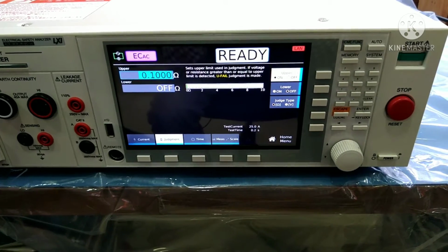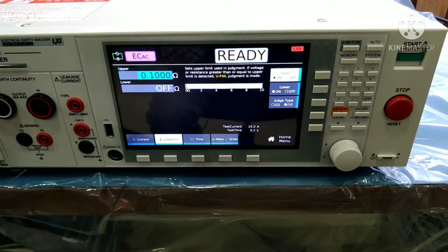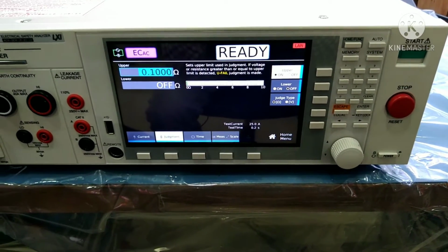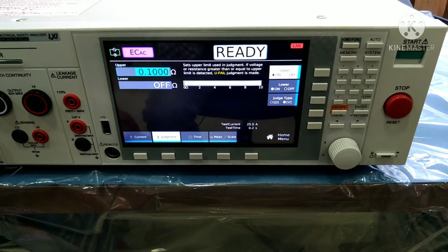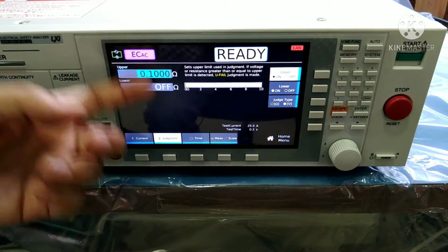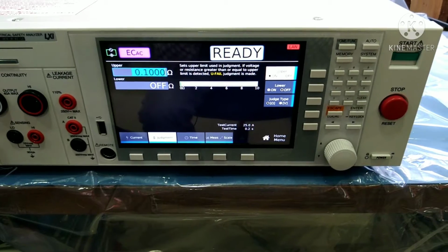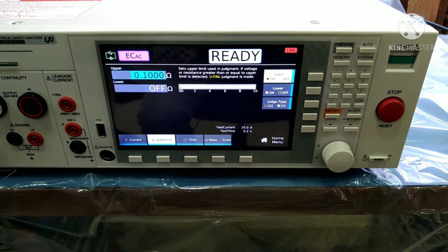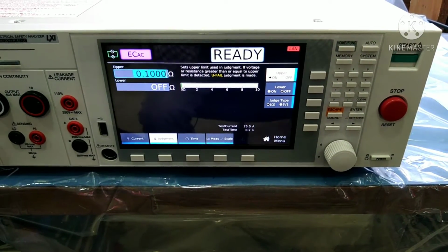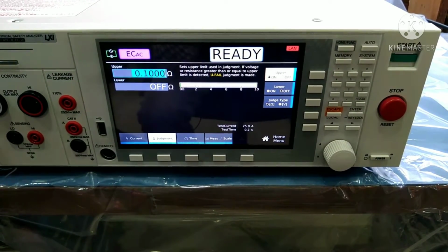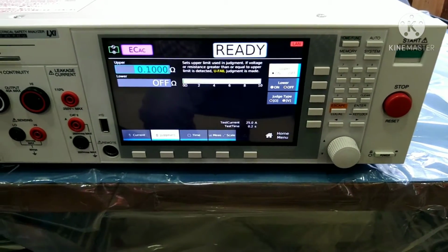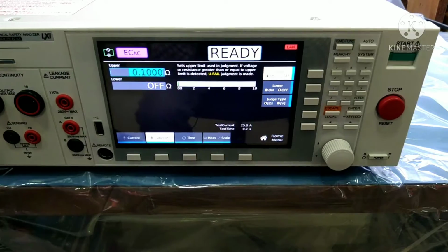If the earthing resistance is low, that means the voltage drop through that circuitry will be low. So the limit should be within 0.1000 ohm, that is very low. So the test resistance should be below this reading. If it is a pass, the quality of the resistance is very good, excellent.